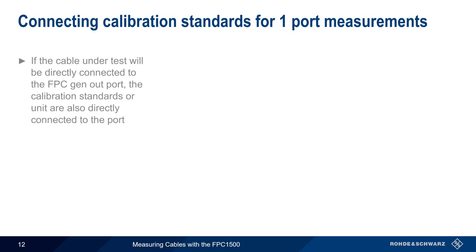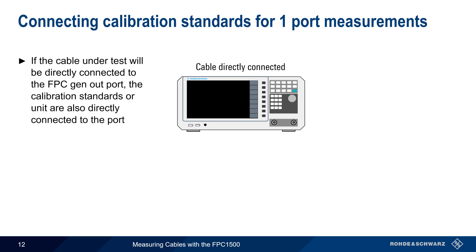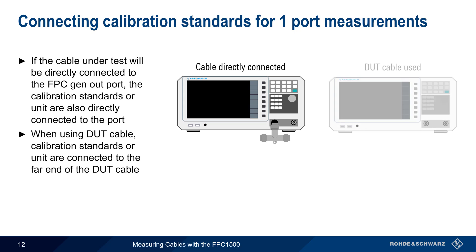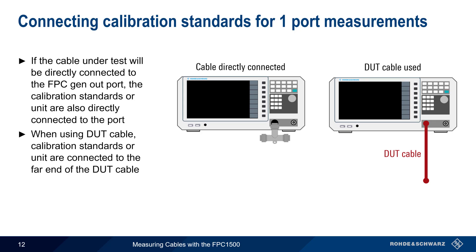If the cable under test will be directly connected to the FPC, then the calibration standards or calibration unit should also be connected directly to the port on the FPC. If, on the other hand, a DUT cable is used between the FPC and the cable under test, then the calibration standards are connected to the end of the DUT cable, since this is where the cable under test will be attached. Note that calibrating at this point will remove the effect of the DUT cable from the cable measurement.